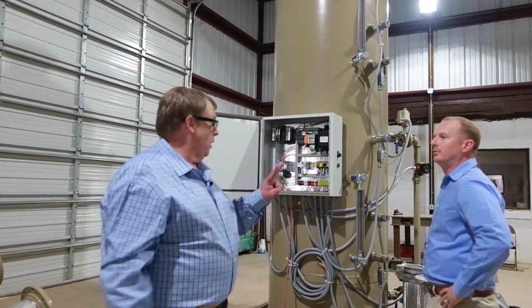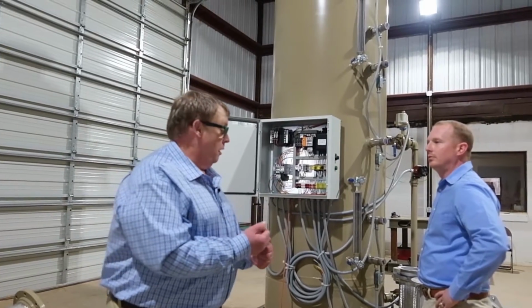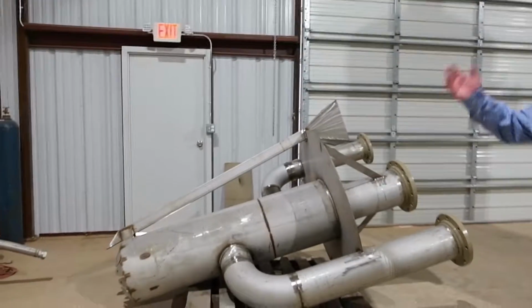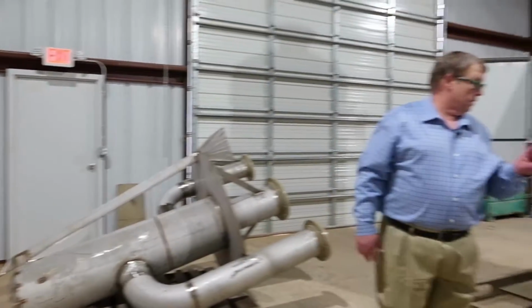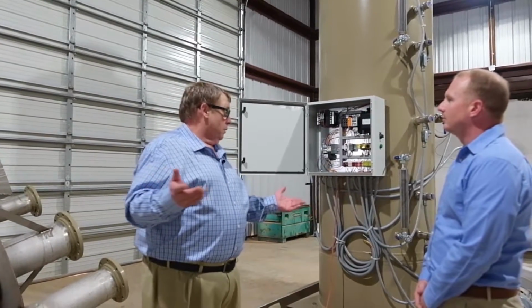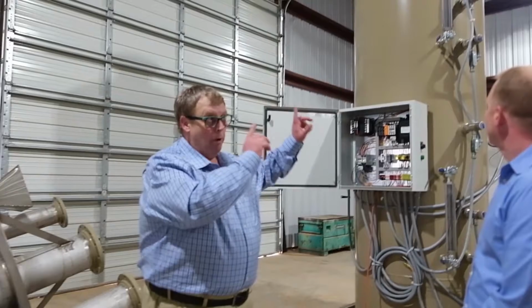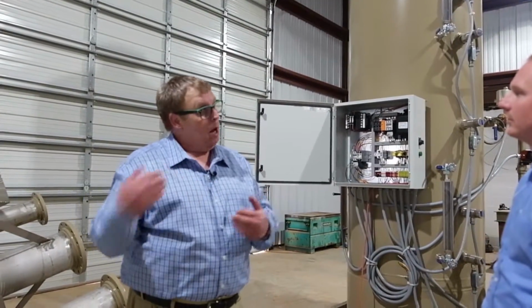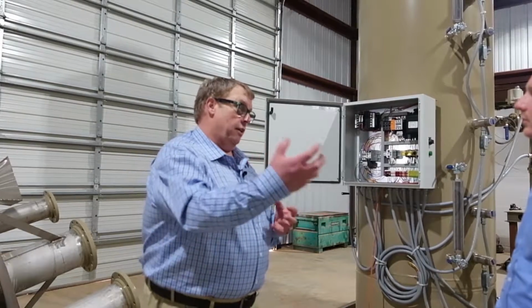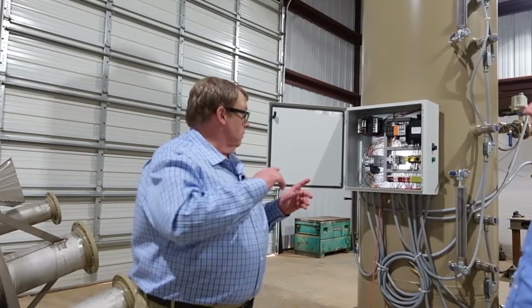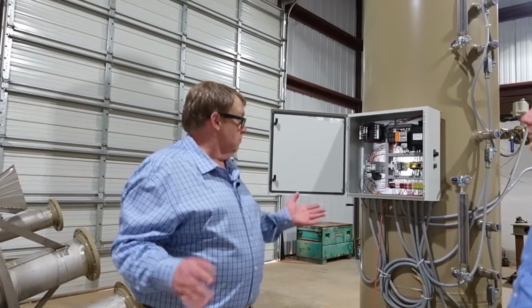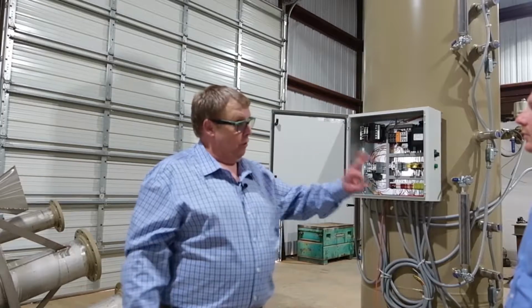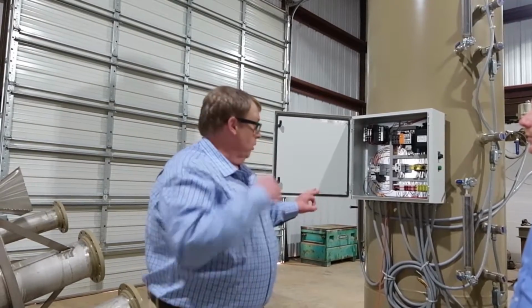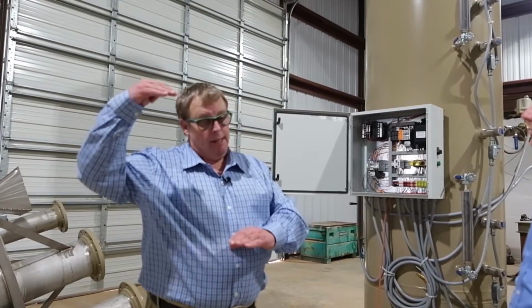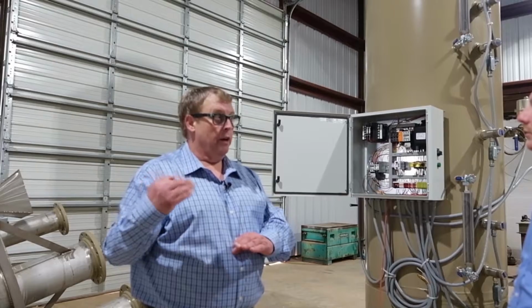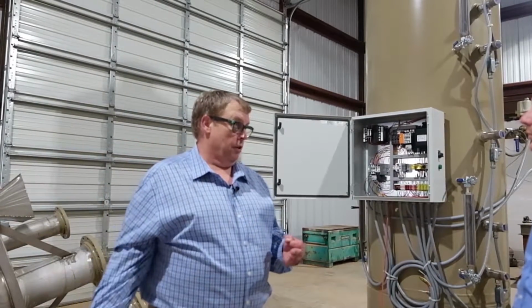And just to recap, there's two items that we're trying to reach here. One is zero emissions, and we're accomplishing that through the air-assisted flare tip. So we've gone over that, as well as the second being proof of pilot. Just to clarify on that, we use a thermocouple up above the pilot that's going to present an output to the Moore transmitter, which is going to take that input and then convert it to 4 separate outputs, depending on what you're using it for. In our case, we're going to use one of those outputs to control the ignition assembly. We're going to want to control that to make sure that we are burning, and that if we have some reason lost pilot or created an event, that would be properly recorded for the energy company.